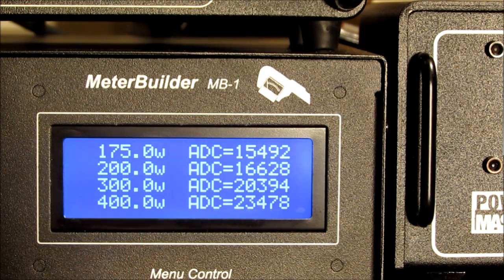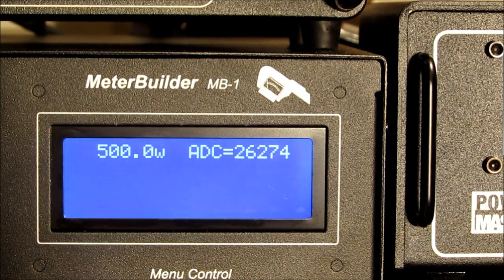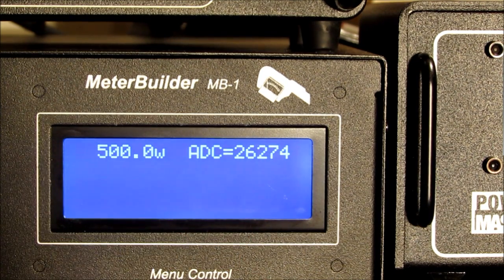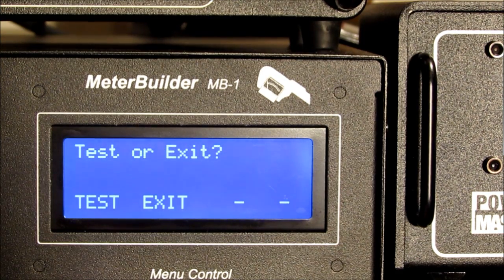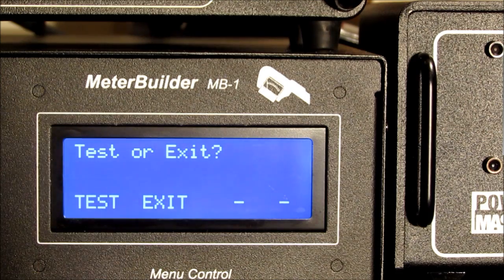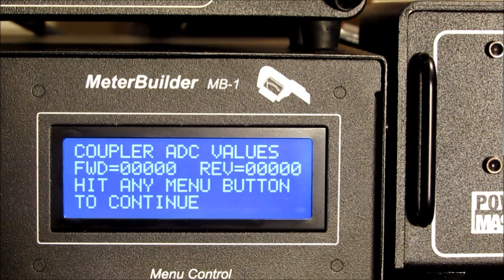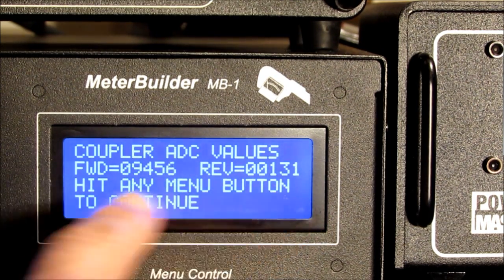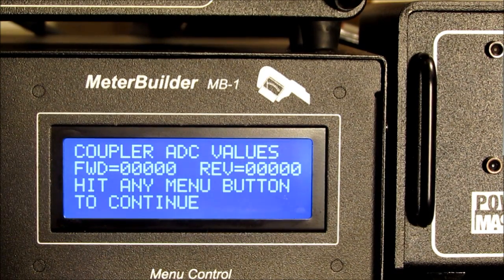You can see we calibrated at 200, 300, and 400 watt points. And again, that's not always necessary, and that's our highest ADC that we were able to achieve with the pot at the full scale value. There are no band correction factors stored for this coupler. Test, exit. Test gives you simply a continuity check, and if I go ahead and hit test, it's showing me what the ADC values are coming into the port. So really it's a simple continuity check to make sure the coupler is connected, and when you apply power you can see an ADC value that you think is reasonable. So it's a test function in that respect.